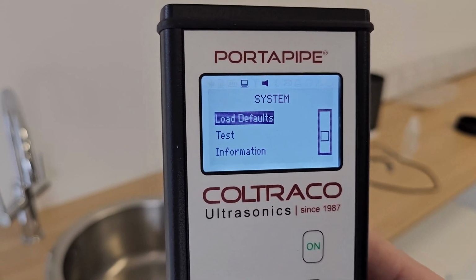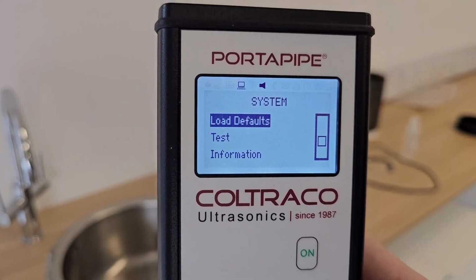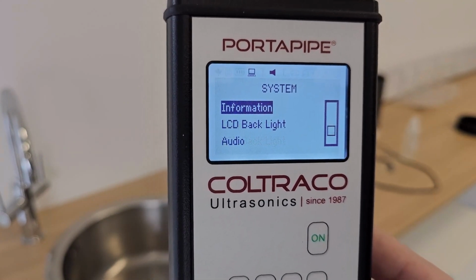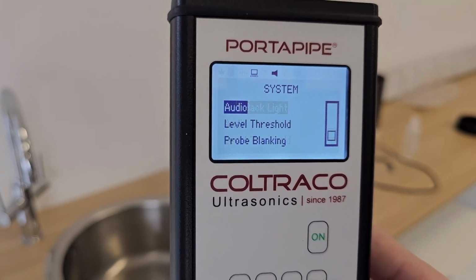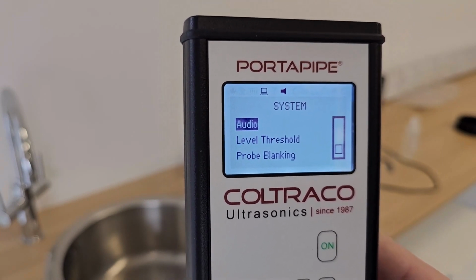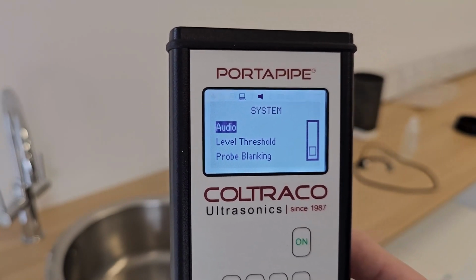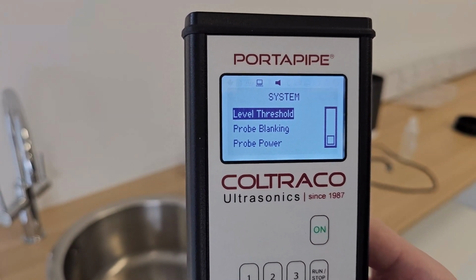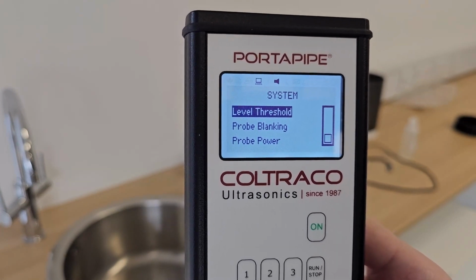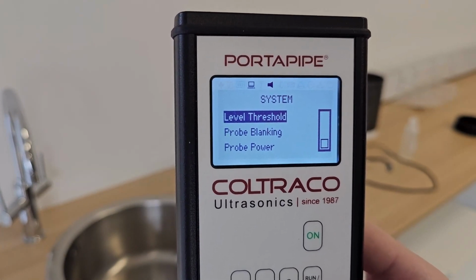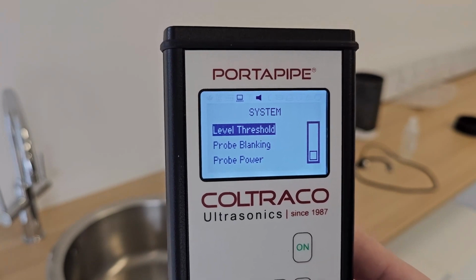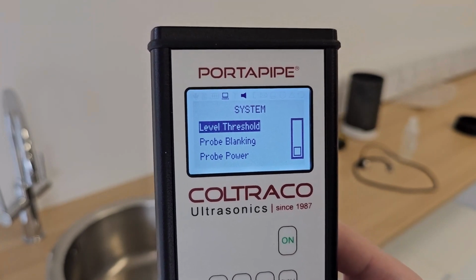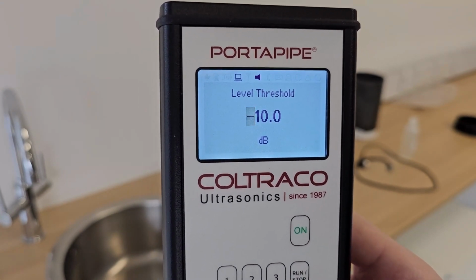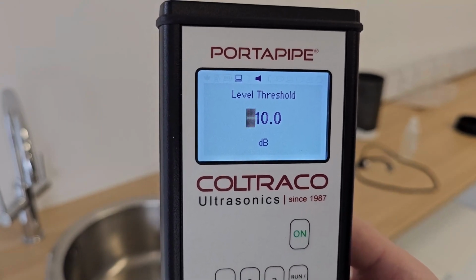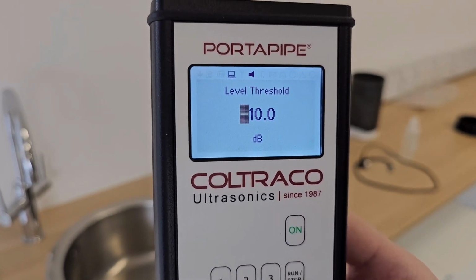Load defaults, which just resets all the settings to their default values. Test, information, LCD backlight and audio are all just about various other parameters on the device. They're not to do with the actual level measurement process. And then we have at the bottom here, we have level threshold, which simply sets the amplitude of signal that this device needs to detect in order to identify that as a potential reflection. We have this set for now to -10, and if we need to adjust that later we will do, and we'll talk about why you might need to do that.